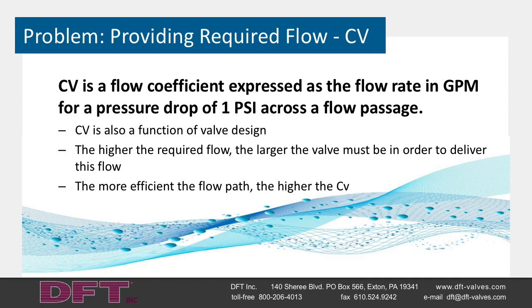Problem: providing required flow — CV. Providing the required flow to satisfy the system conditions is a baseline requirement of any control valve. CV is a flow coefficient expressed as the flow rate in gallons per minute for a pressure drop of 1 PSI across a flow passage. CV is also a function of valve design. The higher the required flow, the larger the valve must be in order to deliver this flow. The more efficient the flow path, the higher the CV.